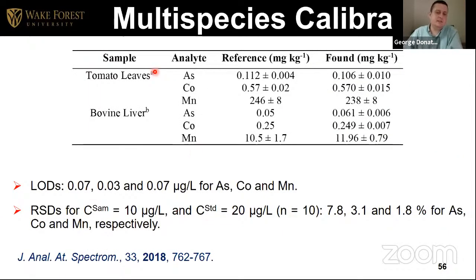And here is the application to bovine liver and tomato leaves for 3 monoisotopic elements, where we use oxides and ammonia cluster species to do the calibration. LODs, usually, as I said, are a little higher than the normal calibration, but still 70 ppt, 30 ppt is not bad at all to measure those elements. And RSDs can be a little high sometimes because of the variation in the reaction cell, but for a quadrupole ICP-MS it's not that bad.